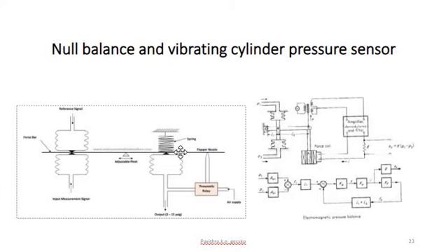So this force bar should always stay in equilibrium. If any change causes a disturbance to this equilibrium, then the output pressure from this bellows will go on increasing until this force bar is back into equilibrium. So here, when we apply the measurement signal, the input signal, to this side, the imbalance takes place, and due to the imbalance, what will happen?